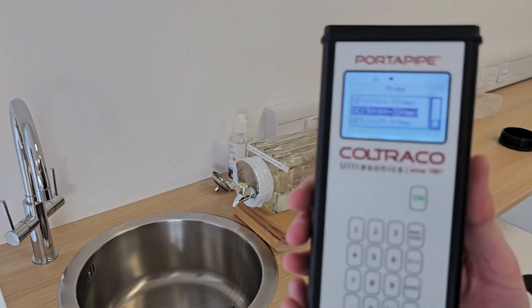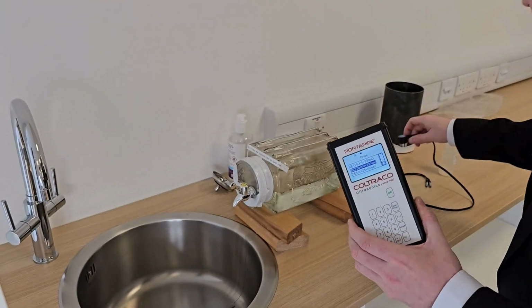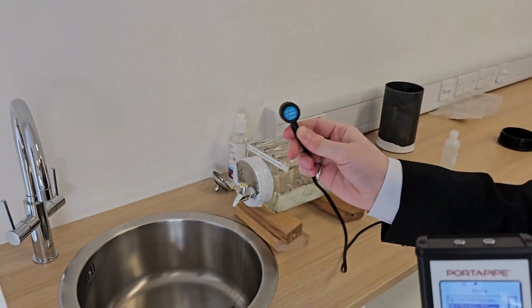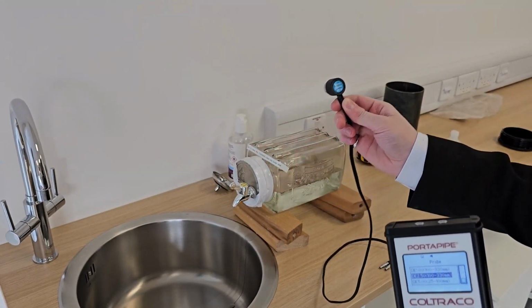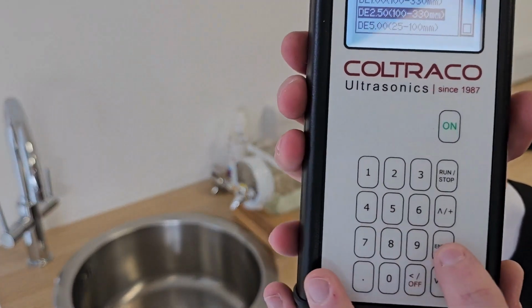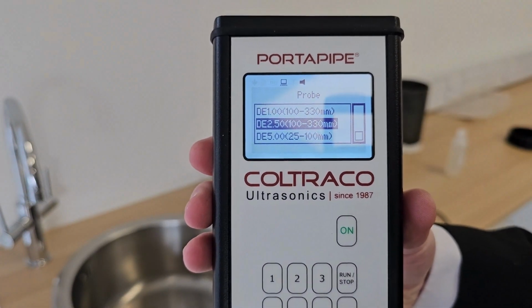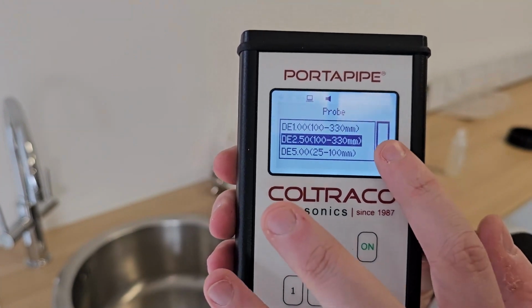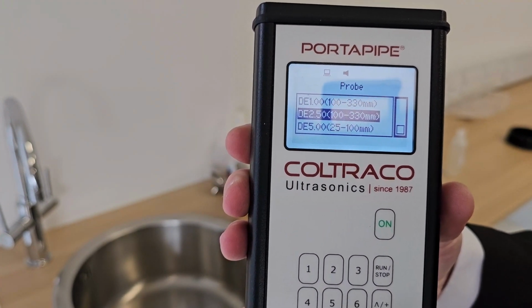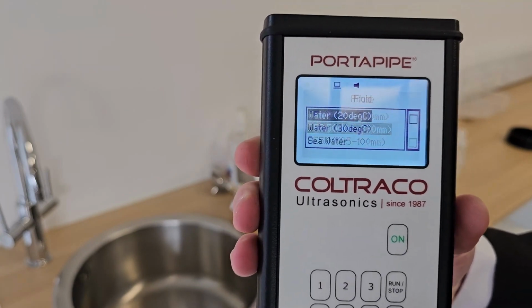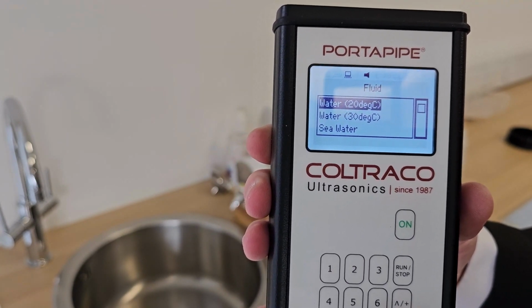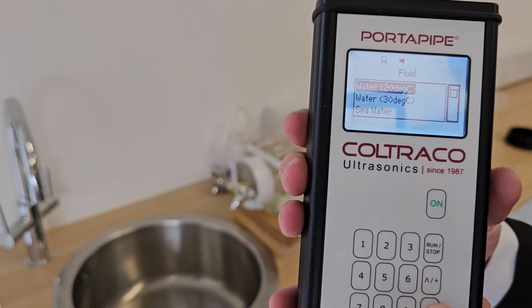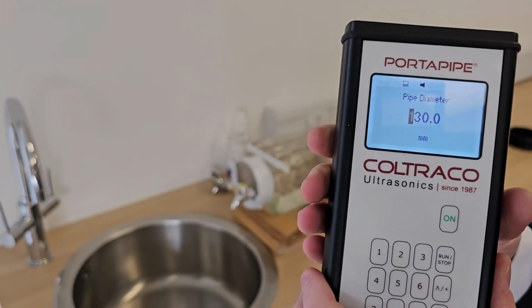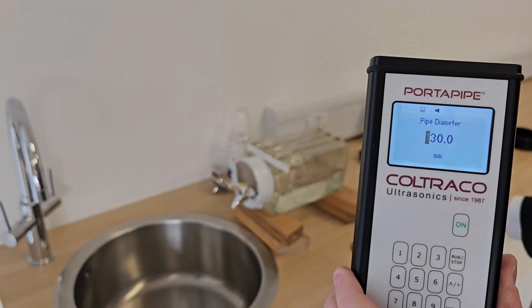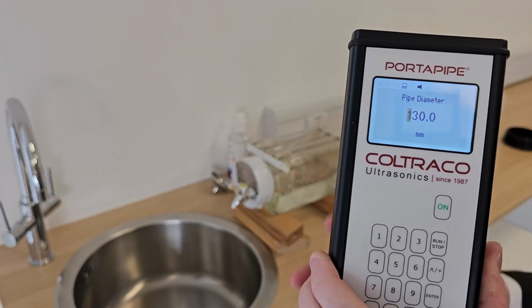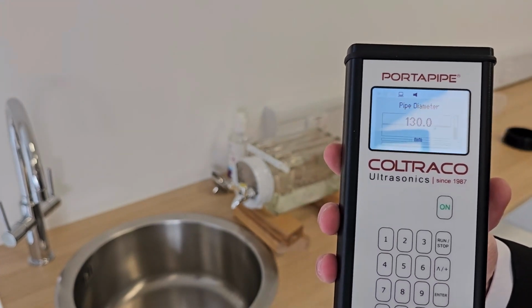So it's going to ask us what probe we're using first of all, and today I'll be demonstrating using a 2.5 megahertz, 14 millimeter diameter probe. So I can select on the screen here the 2.5 megahertz probe, DE 2.5, and you can see that's recommended for 100 to 330 millimeter diameter containers. And then I will select our fluid, which is just room temperature water in this case, so water at 20 degrees. And then the pipe diameter I input earlier, I've measured this with the tape measure, and that is 130 millimeters. So press enter. And now we're ready to start measuring.